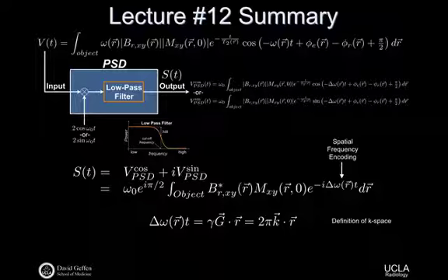And this is kind of the magic of MR. This is what Lauterbur basically got his Nobel Prize for, recognizing that if you take the state of the transverse magnetization, apply some gradients, and by applying gradients, sample a particular spatial frequency, you can evaluate this complex valued function at a particular K point. And now you just have to get all your K points so that, after a Fourier transform, you come back to having an image.